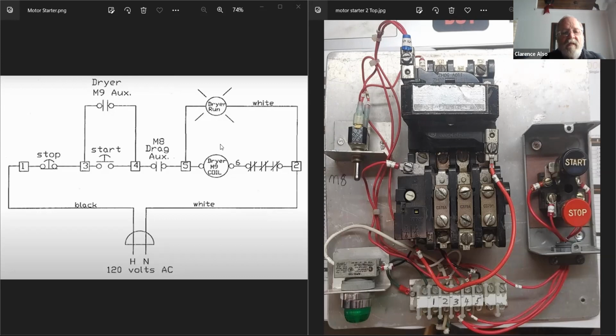Okay, I'm gonna save a real fun one here. Strap in. I'm pressing the start button, and the coil chatters to beat hell. I don't know if you've ever heard these coils in the starter cabinets buzzing, but this is buzzing bad - it's just kind of clattering along to a point where you're going, damn, I'm gonna burn up this motor and those contacts if I let this thing do this, because the contacts are coming in and out. Do we have a video to show that, David? Yeah.